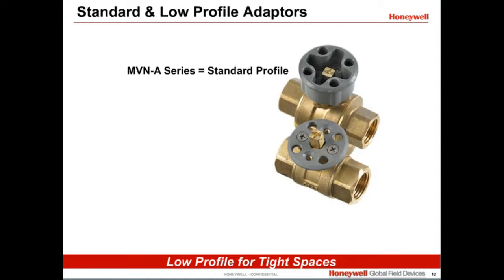The MVN actuator is available in 2 different versions, a standard profile A series and a low profile L series. The standard profile model can meet the needs of most tight space applications, but for applications with extremely tight spaces, the low profile is available. It is important to know that the actuator is slightly different for the 2 profiles, so it is important to use the correct profile valve with the correct actuator.